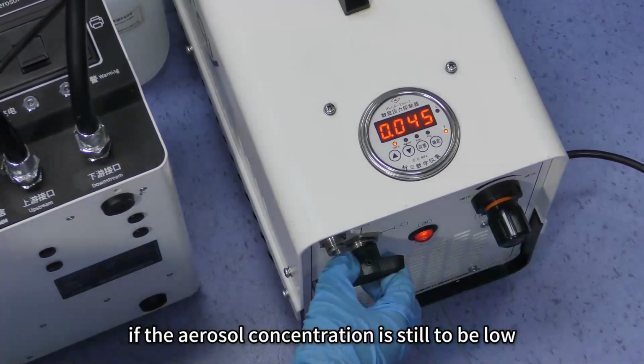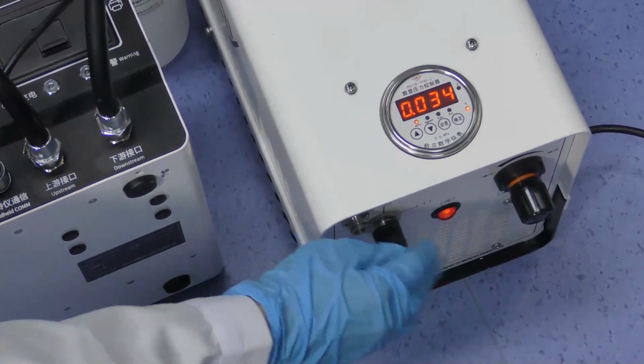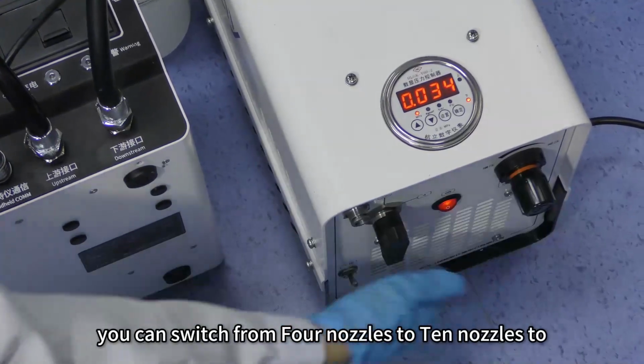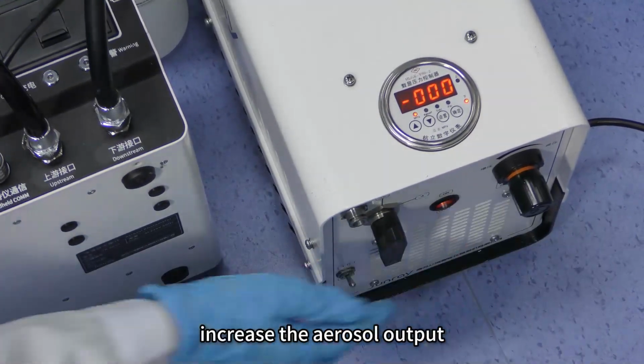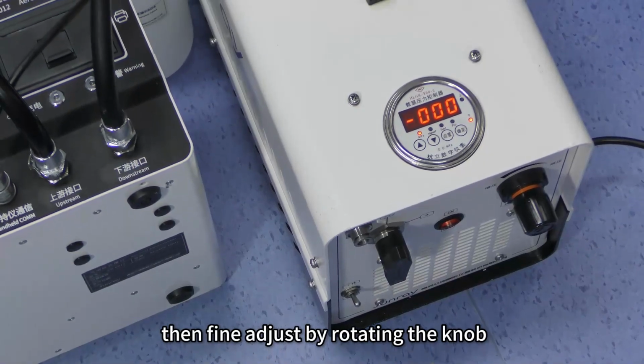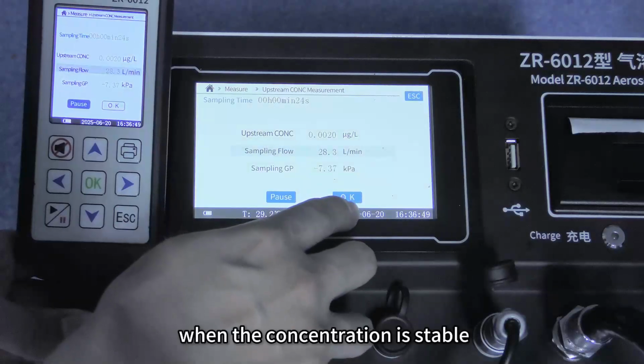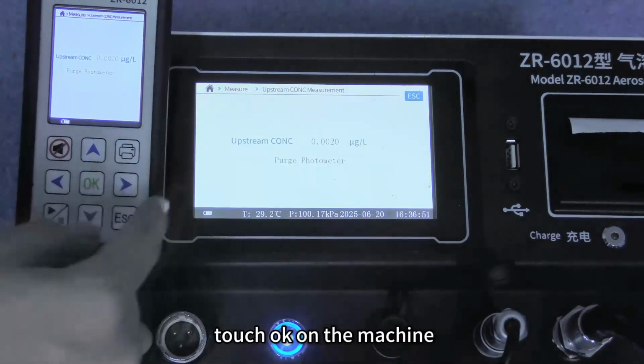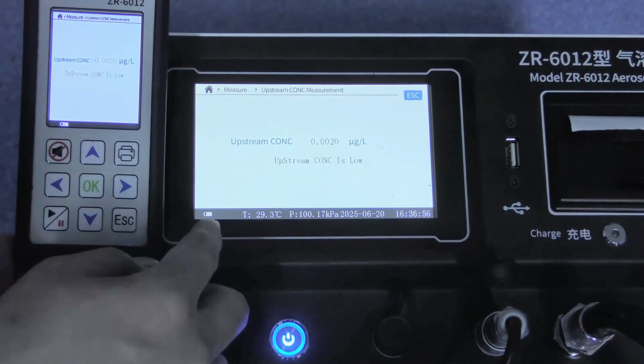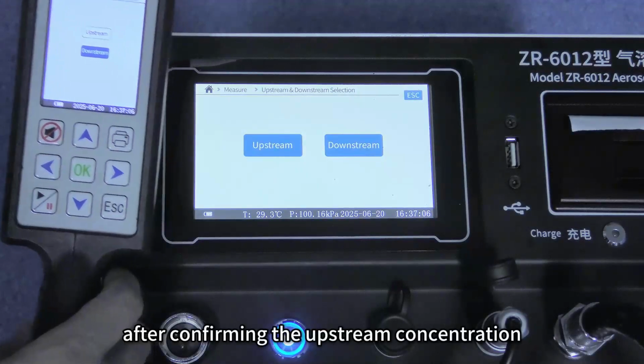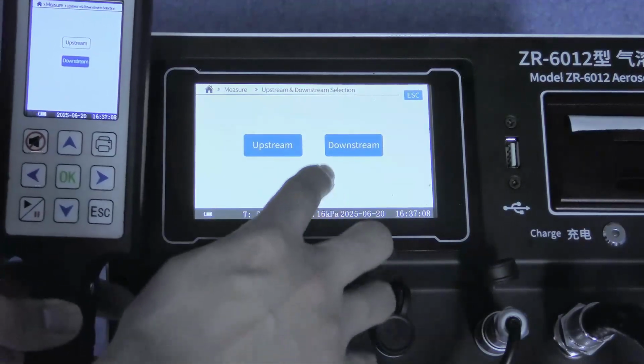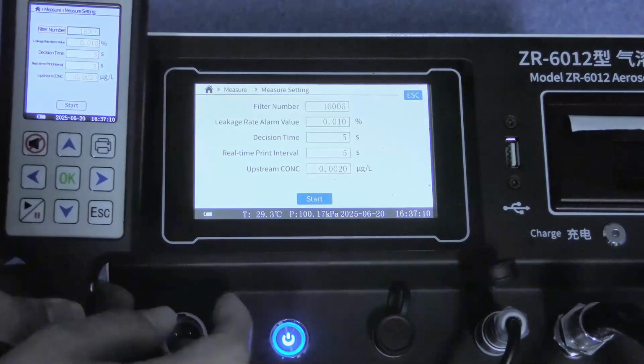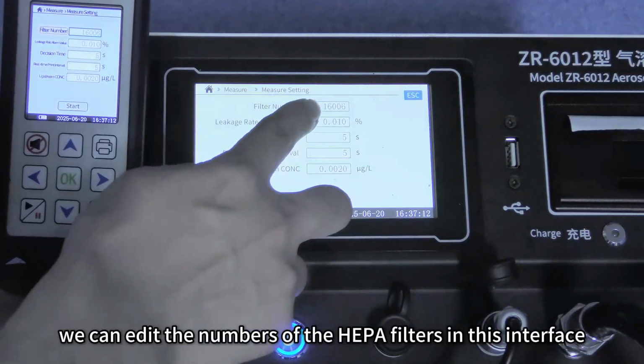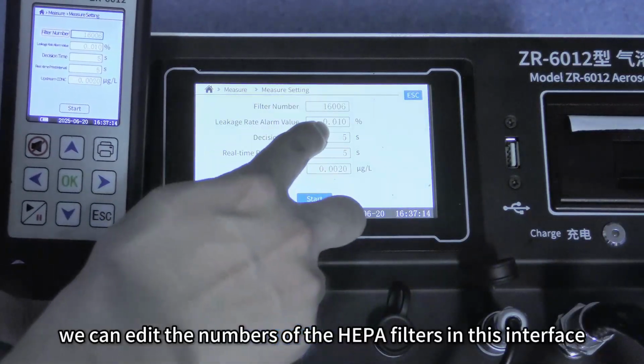If the aerosol concentration is still too low, you can switch from 4 nozzles to 10 nozzles to increase the aerosol output. Then fine adjust by rotating the knob. When the concentration is stable, touch OK on the machine. After confirming the upstream concentration, we can touch downstream. We can edit the numbers of the HEPA filters in this interface.